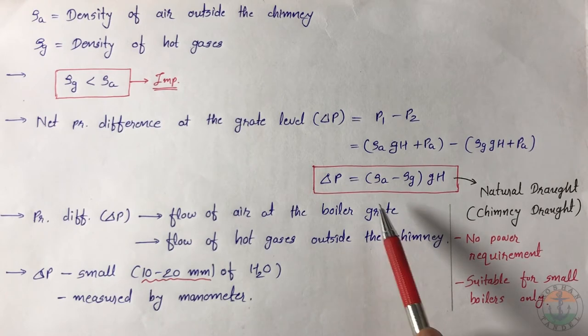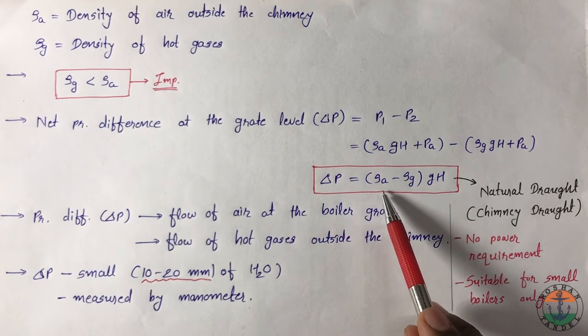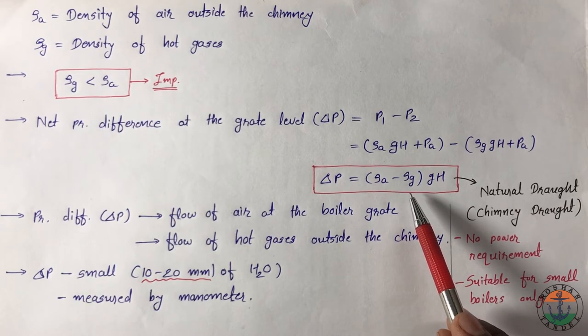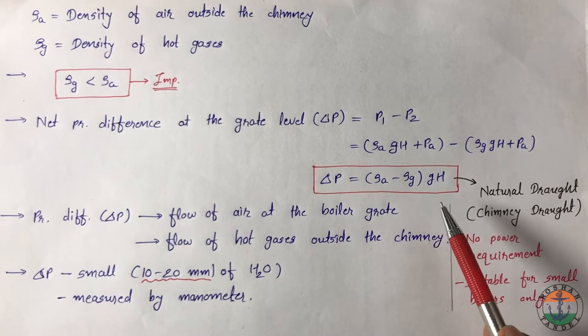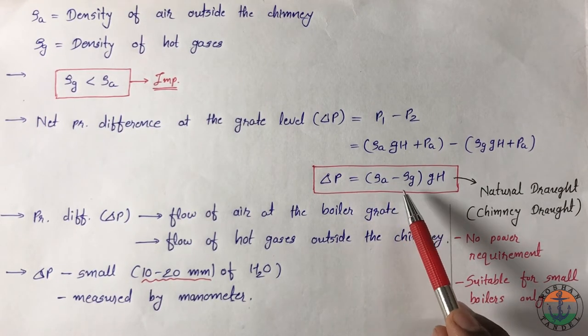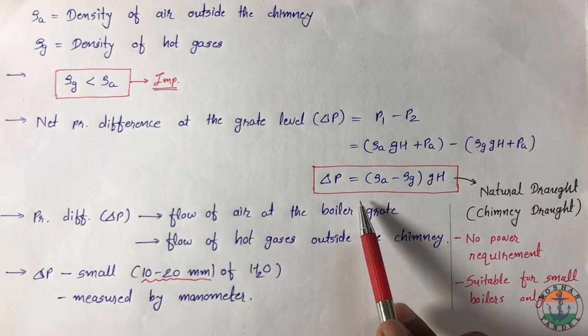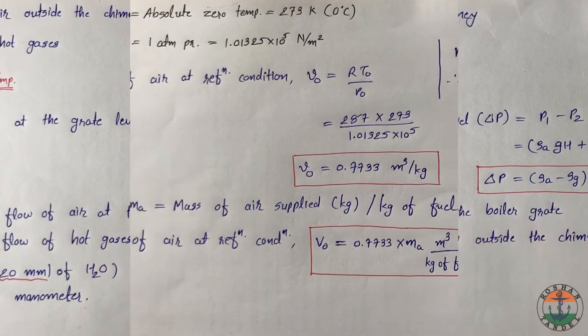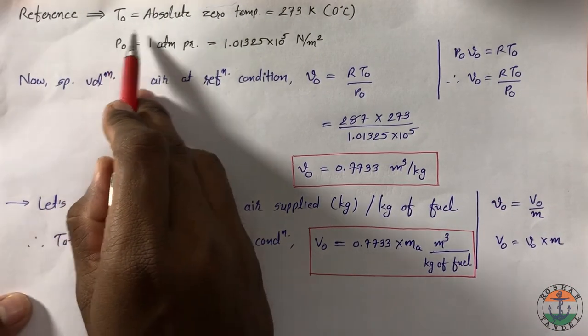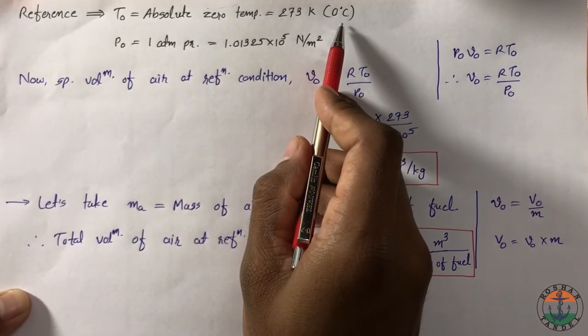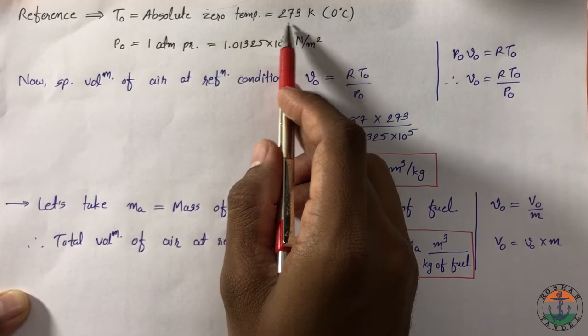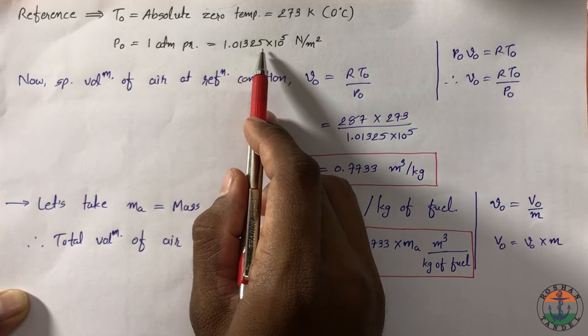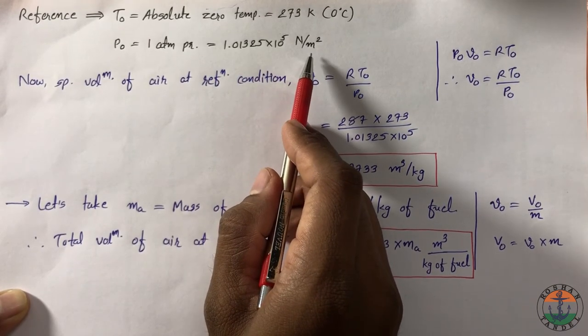We have the natural draft equation in terms of density of air and density of flue gases. We are going to convert it in terms of temperature of cold air and temperature of flue gases, so that with the help of temperatures we can easily calculate delta P. For reference, T0 is the absolute zero temperature, 0°C or 273 K, and P0 equals 1 atmospheric pressure, 1.01325 × 10^5 N/m².